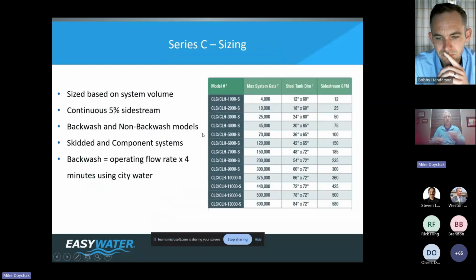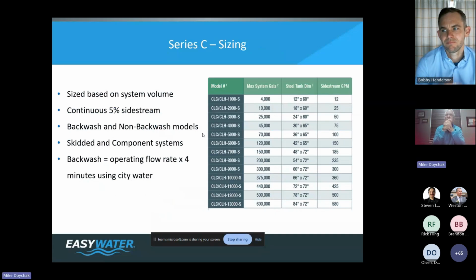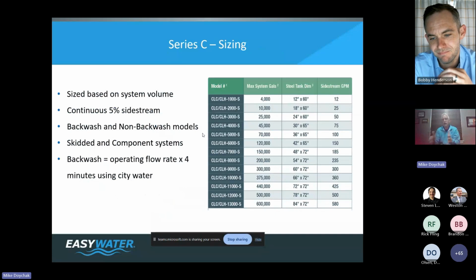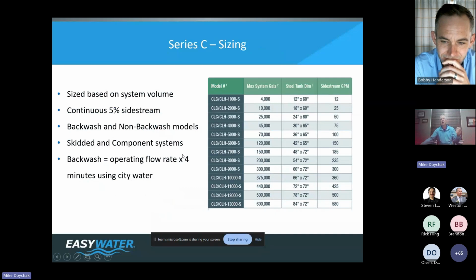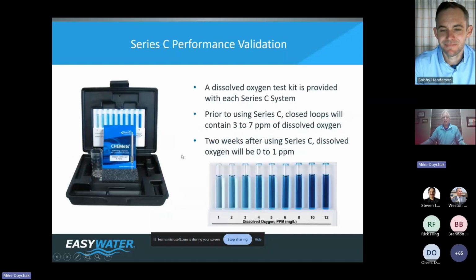Sizing, all very simple. They're all sized the same way. We're going to size them on a 5% side stream, so you can kind of see on the right there what the flows are going to look like. They are sized on system volume. So we're not looking at GPM, we're looking at total volume, and we can help calculate that whenever you need us to. These are the backwashing systems. One thing I do want to bring to your attention, if you use the backwashing system, know that your operating flow rate, whatever the unit's operating at, is going to be the backwash rate as well for 4 minutes. So just make sure there's an adequate drain or whatever to handle it.